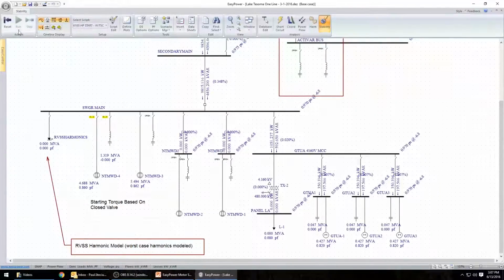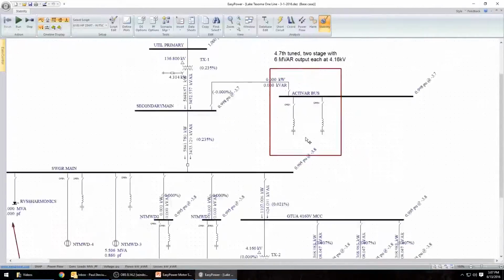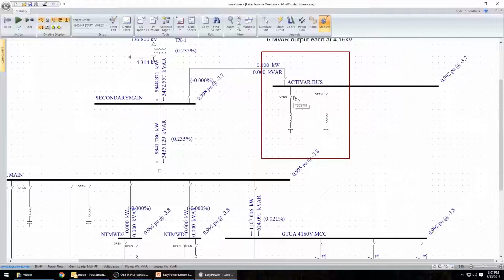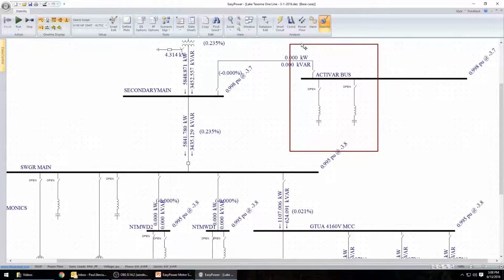So essentially what I've done is I step through the analysis, and I find at what point in time the voltage gets to where I need it to get to, and then I edit the script and open the TSC stages at that point in time. I've also used overvoltage relays, associated with the switches here, and had those overvoltage relays trip the associated switch at the time where the voltage rises above 1.05 per unit, and then I time coordinate these overvoltage relays. I have found that the effort isn't worth the output, and it's easier just to step through the analysis similar to what we have done before. I can go back and do that. Oops.